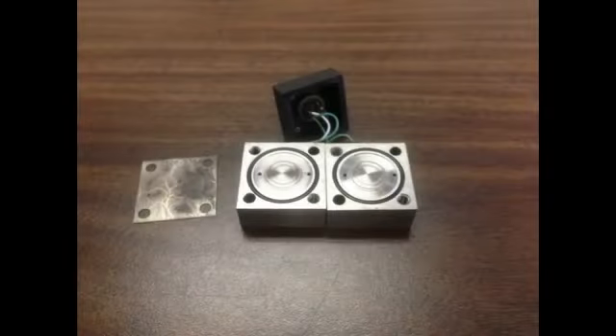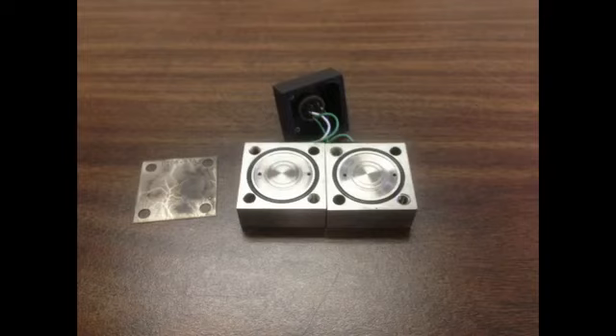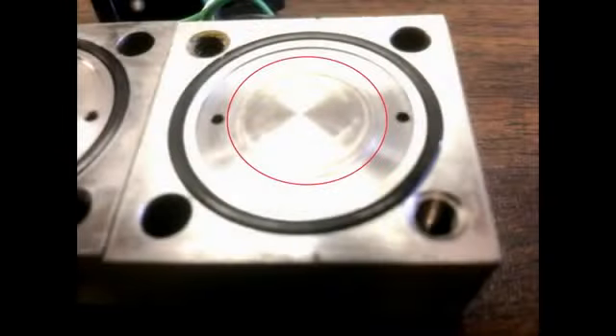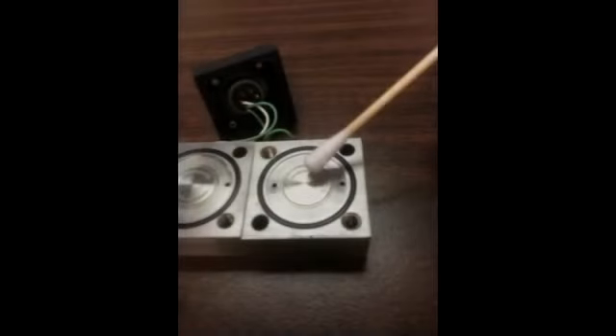Now look closely at the center of the inside of each coil housing. You will see a dime-sized foil lid that has been welded in the center of the sensor cavity. Using a magnifying glass, check to see that this weld is intact. Corrosion often attacks this area and this can cause lack of isolation or loss of continuity.